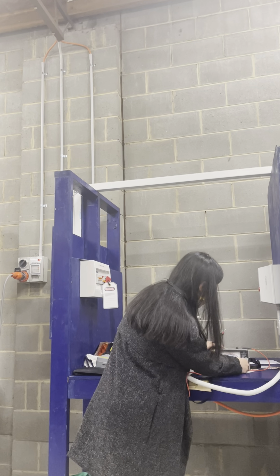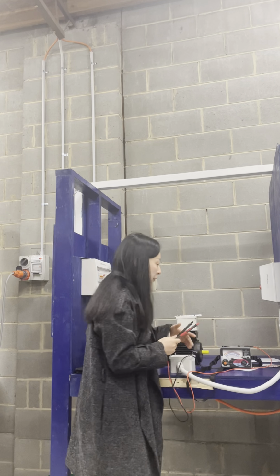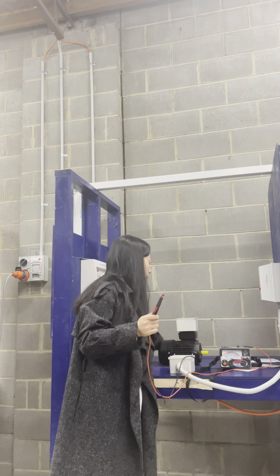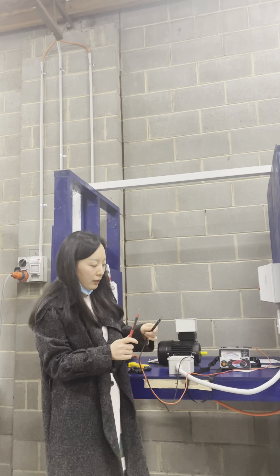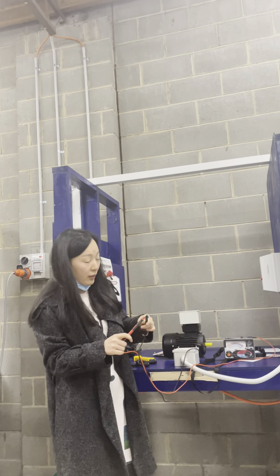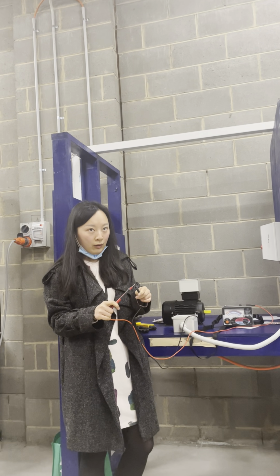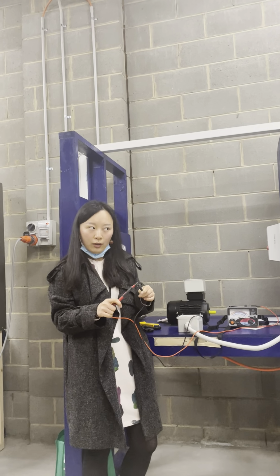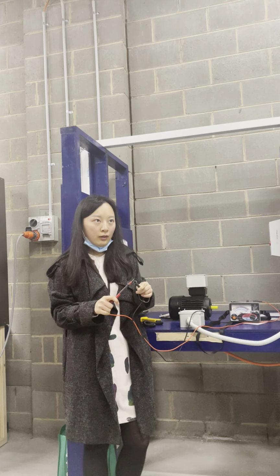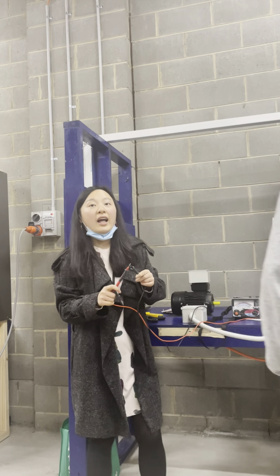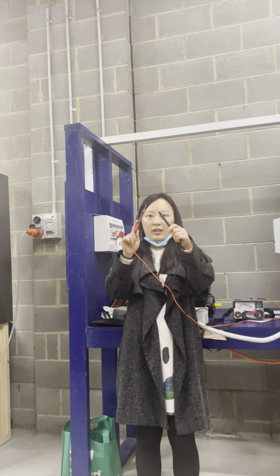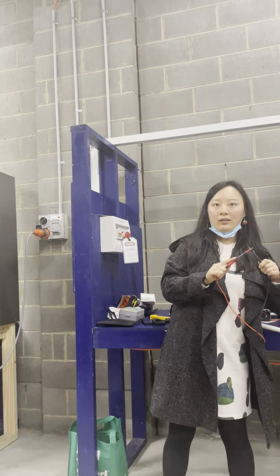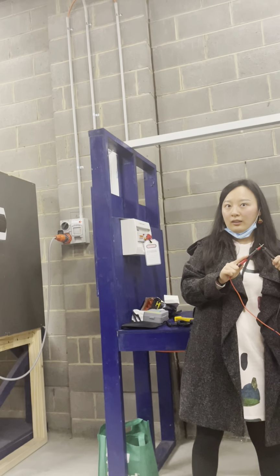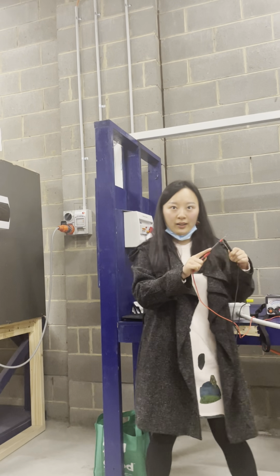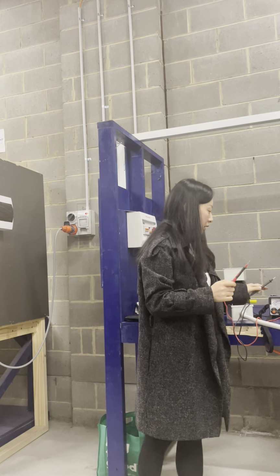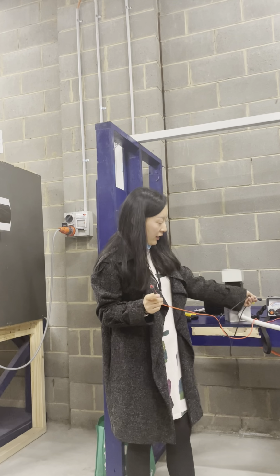Okay. So let's go back. 500 volts, 200 mega ohms. Test your tester first. What's the value? Infinity. No. Zero. Yeah, 0. If you don't watch this, I'm shorting this out. What are you expecting? To go to 0, correct? Because it's a short circuit. It's a loop. So you are expecting 0 mega ohms. Now it is infinite because it's open circuit.